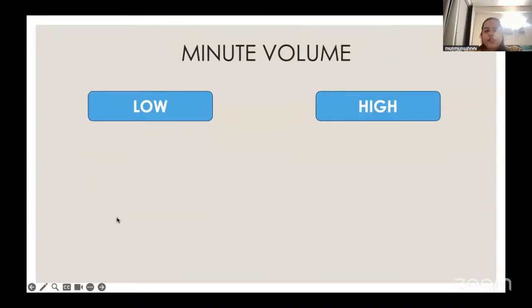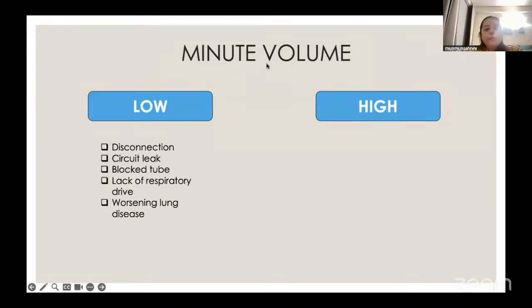So what does low minute volume mean? A low minute volume means that the tidal volume or the rate has been very low. So here the lung is not expanding completely. There may be areas of atelectasis and there may be accompanying retention of CO2. So a low minute volume alarm may indicate that there has been a disconnection or leak, which prevents the tidal volume from being delivered.